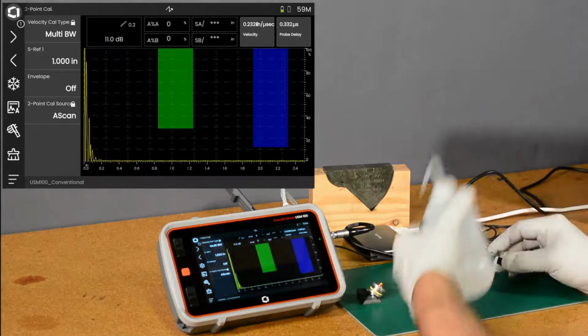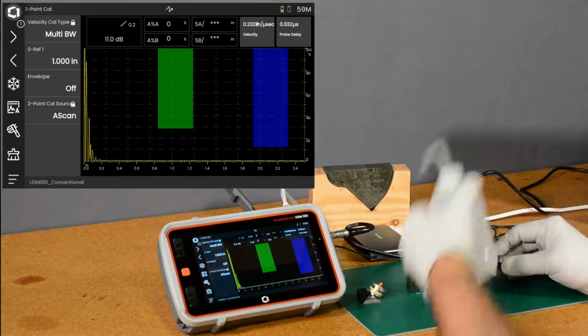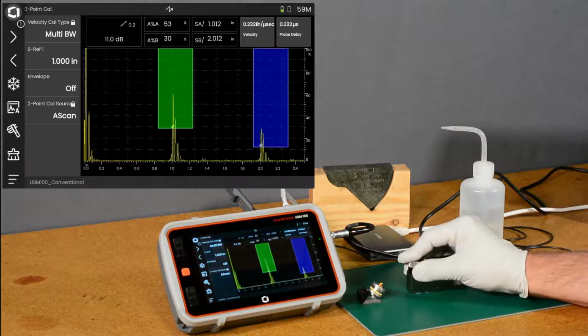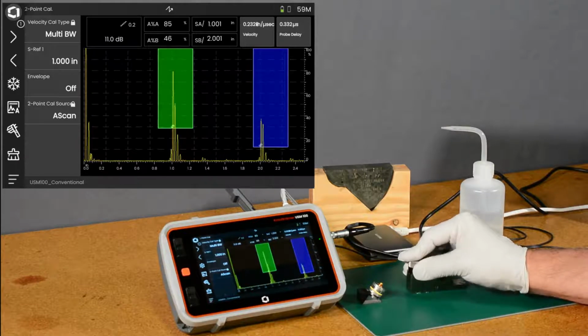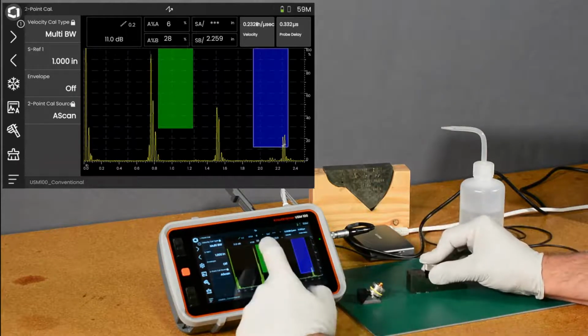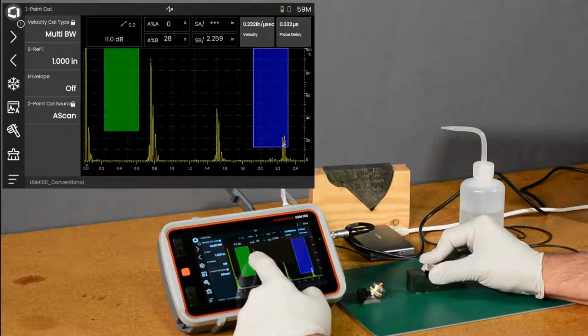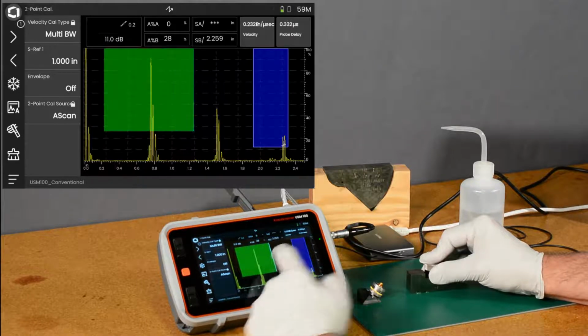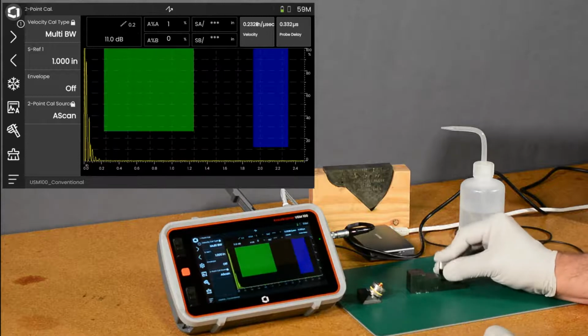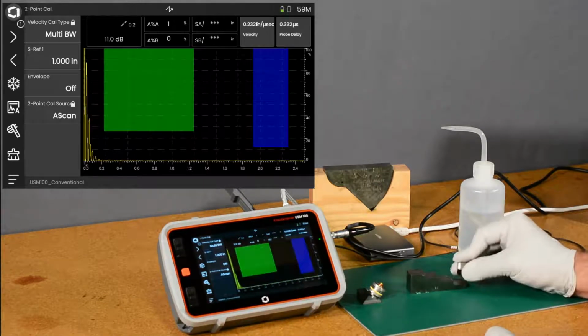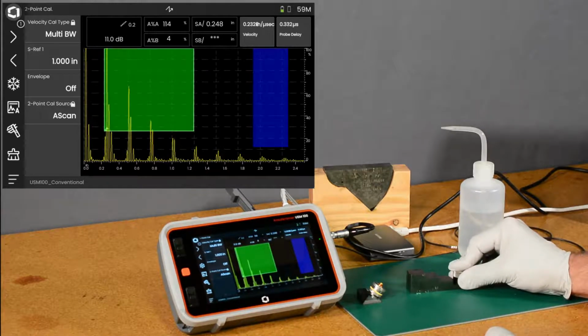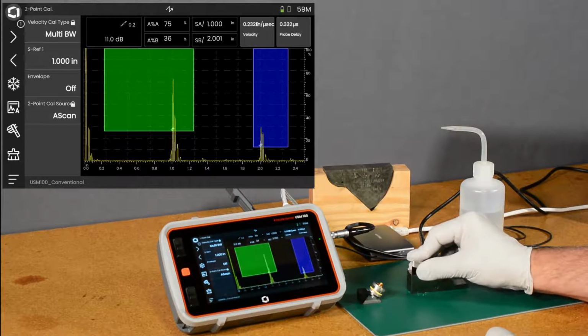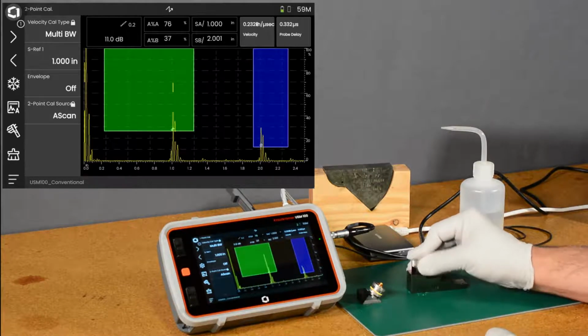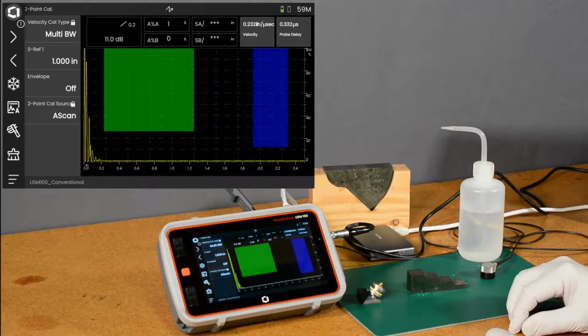Get a little more coupling on here. So there at 1 inch, 3/4 of an inch. Let's drag our gate A here, make it a little wider, so we can measure over the range. 1/2 inch and 1/4 inch. So our delay and velocity calibration completed as we expected.